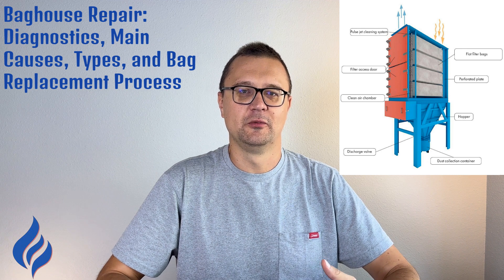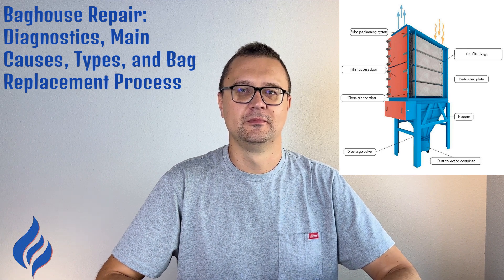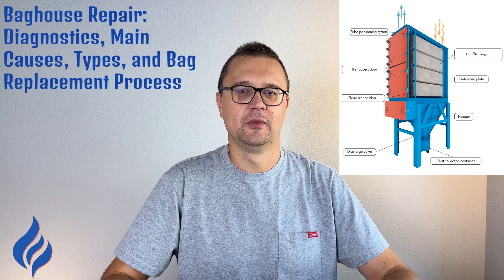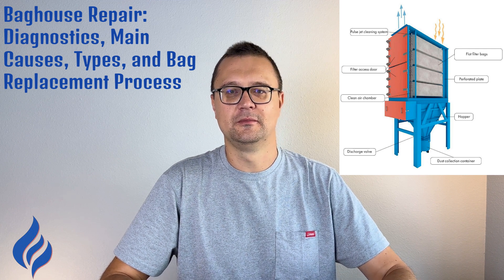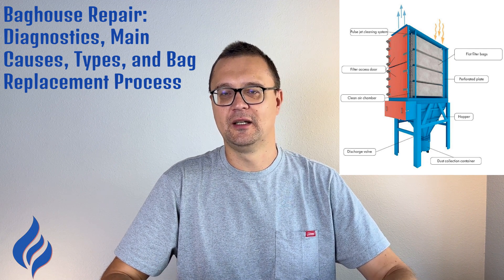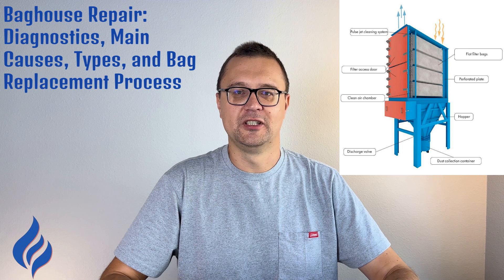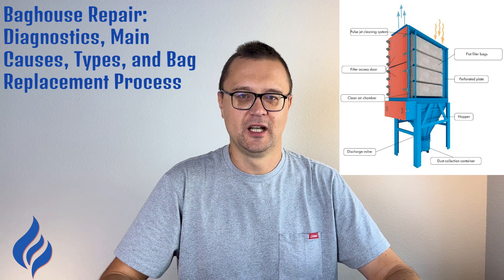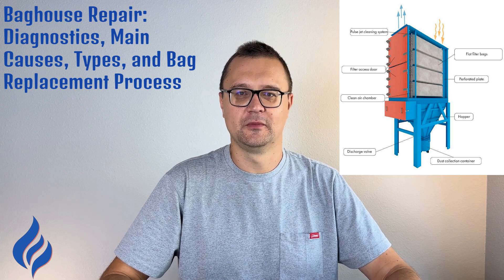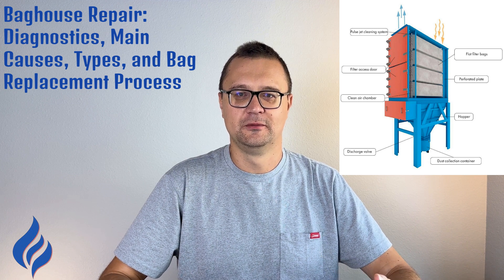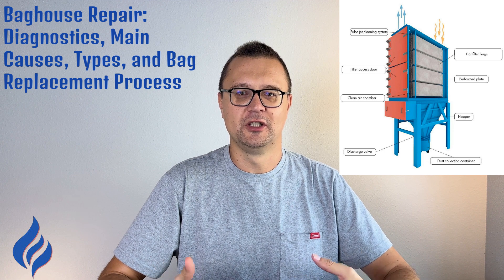The Bag Replacement Process. Let's go over the step-by-step process of replacing bag house filters. Preparation. Before replacing the bags, shut down the system to ensure safety and prevent any pollutants from escaping into the workspace. If your bag house operates at high temperatures, allow the system to cool down. Always use appropriate PPE — gloves, respirators, goggles, and coveralls — to protect workers from harmful dust and chemicals.